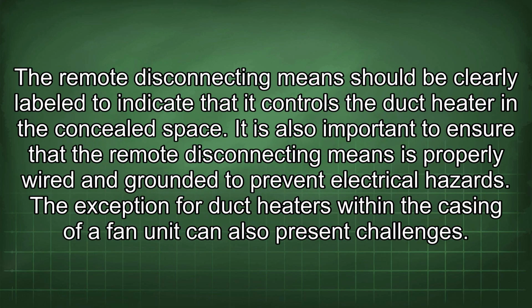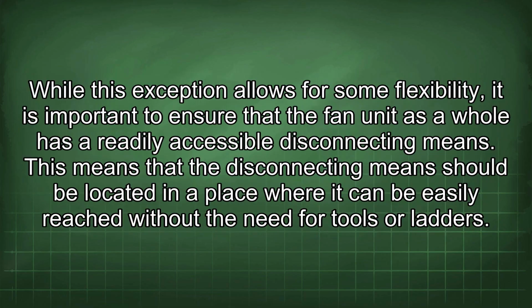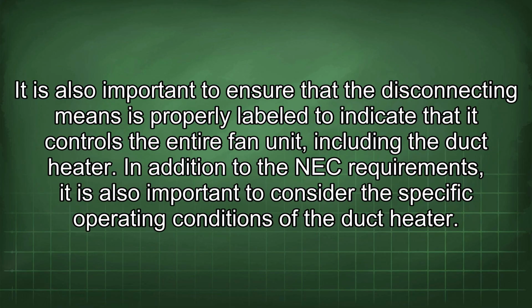The remote disconnecting means should be clearly labeled to indicate that it controls the duct heater in the concealed space. It is also important to ensure that the remote disconnecting means is properly wired and grounded to prevent electrical hazards. The exception for duct heaters within the casing of a fan unit can also present challenges. While this exception allows for some flexibility, it is important to ensure that the fan unit as a whole has readily accessible disconnecting means. This means that the disconnecting means should be located in a place where it can be easily reached without the need for tools or ladders. It is also important to ensure that the disconnecting means is properly labeled to indicate that it controls the entire fan unit, including the duct heater.